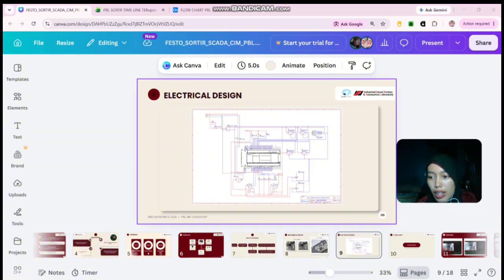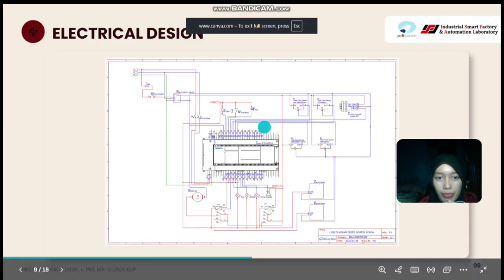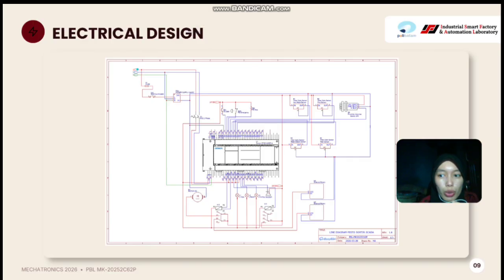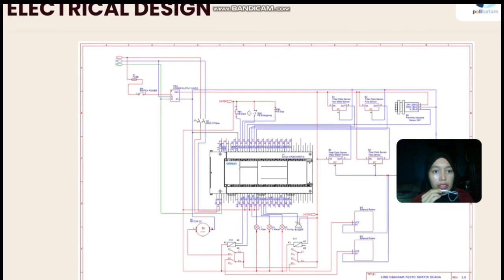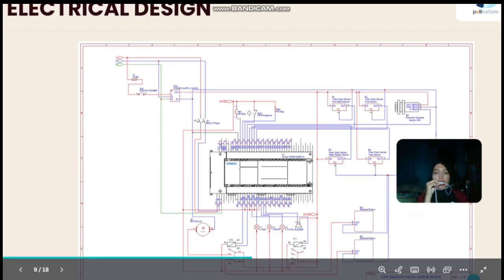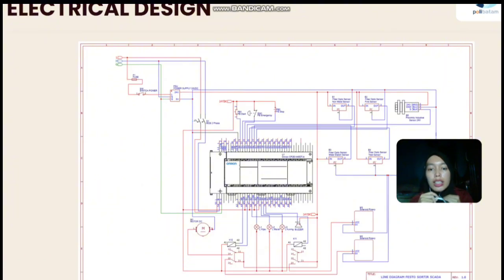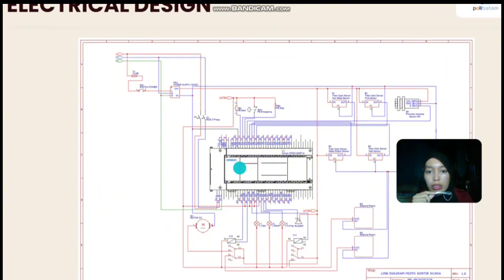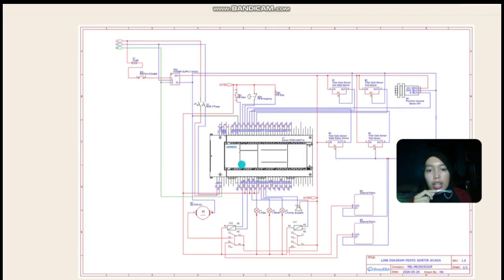Okay, so this is our electrical design. Here's the diagram. We have a main power 220 AC, and it goes to a 24 volt DC power supply as the main power for the sensors and actuators. Then it goes to a fuse and switch power for protection. We must turn on the switch power first, and then we have a 2-pole MCB as protection for the PLC.